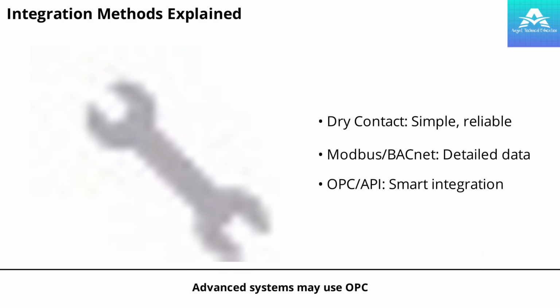There are several ways to connect fire alarm systems with BMS. The most common method uses dry contact simple relay outputs from the fire panel wired directly to BMS digital inputs. For more detailed data exchange, protocols like Modbus or BACnet are used, allowing serial or IP-based communication. Advanced systems may use OPC, API, or SNMP for software-level integration, especially with smart panels. Typically, dry contacts are used for immediate actions like shutting down HVAC, while Modbus provides detailed status updates. Choosing the right method depends on the building's needs and the complexity of the systems involved.